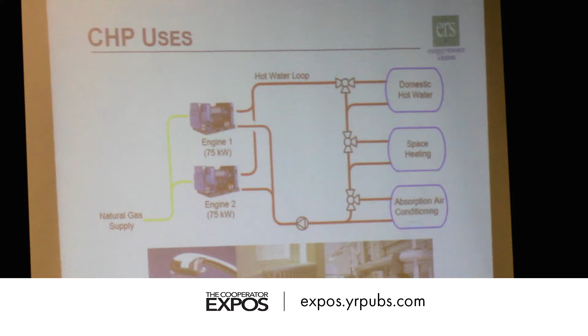There's a type of air conditioning known as absorption air conditioning that actually operates on a refrigeration cycle using heat. So with the right circumstances, it can be a good complement to your building heat in winter and provide year-round use of thermal output — heating in winter and air conditioning in summer through absorption chillers. A lot of central and lower Manhattan that's on Con Ed steam takes advantage of absorption chillers, so it's well known in those geographical areas.